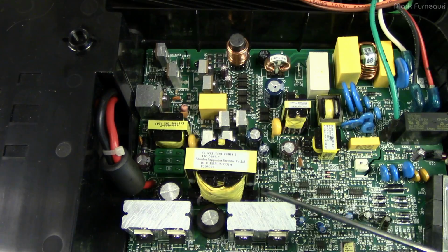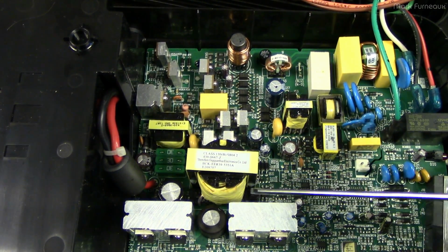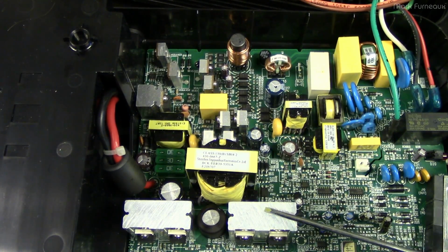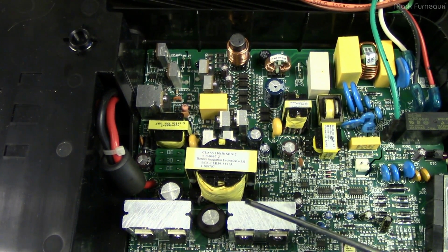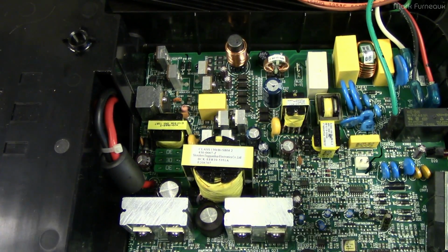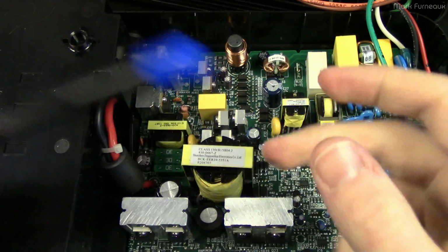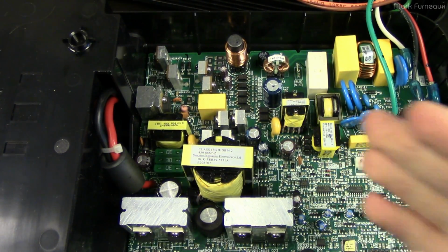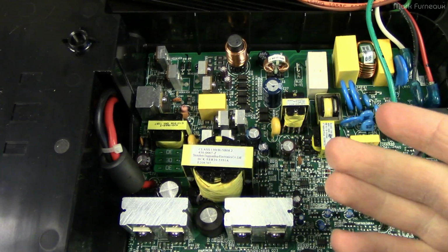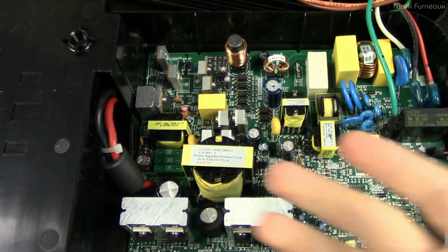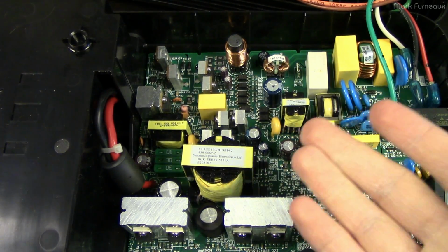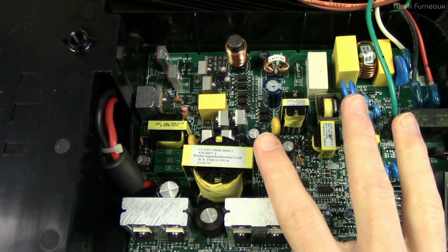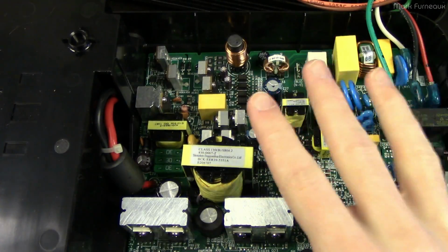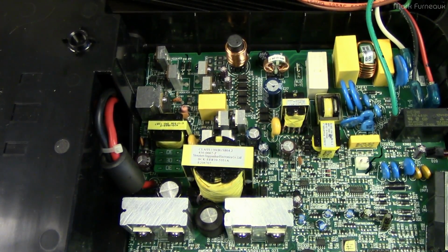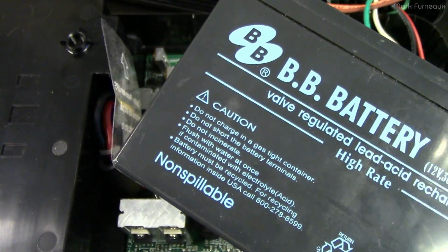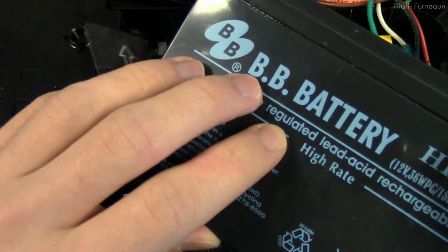The reason is because they don't actually want to reject the heat from these parts into the environment—that's not actually the goal of these devices. Because, of course, this is a UPS. So when the power fails, the job of this is to supply power for a short period of time until whatever's plugged in can be shut down or the power comes back on. So the idea is that the amount of power that flows through this inverter is fixed to the capacity of whatever the battery is in here, right? So there's a fixed amount of energy in this.